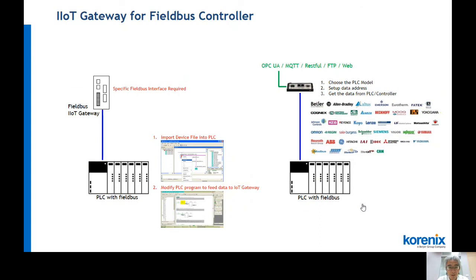We know the Modbus gateway is much easier, but for the PLC controller, sometimes we need the gateway, just like a device driver, because the Fieldbus gateway sometimes requires modifying the program in the PLC. If it's an existing operating factory where the PLC is already controlling something, and you want to stop it to add a program, it cannot be accepted because the user will worry about it affecting operation stability. But for the PLC driver, like the HMI, we just plug and play, so we don't modify anything for the controller and we can still get the data. That's a very perfect solution for an existing operating factory. We get the data and can send it to the IT side like OPC UA, MQTT, RESTful API, FTP, or a WebView website. So that's the PLC gateway in Beijer Electronics.